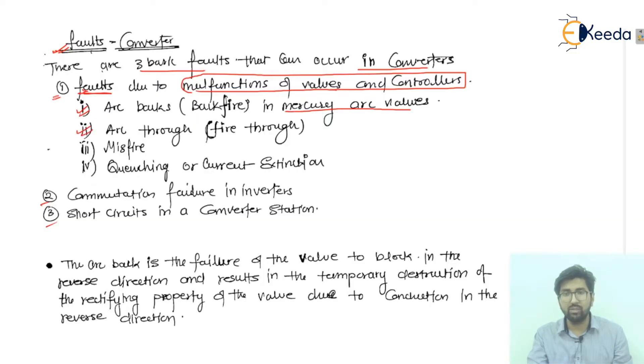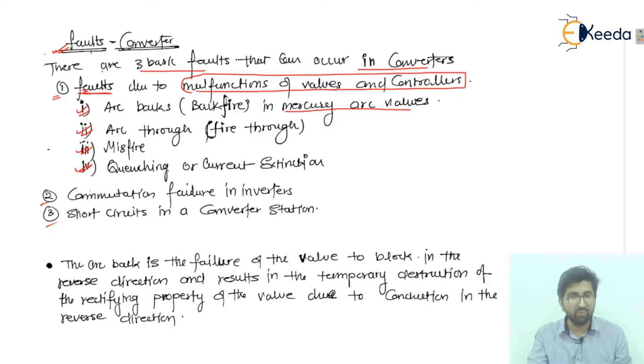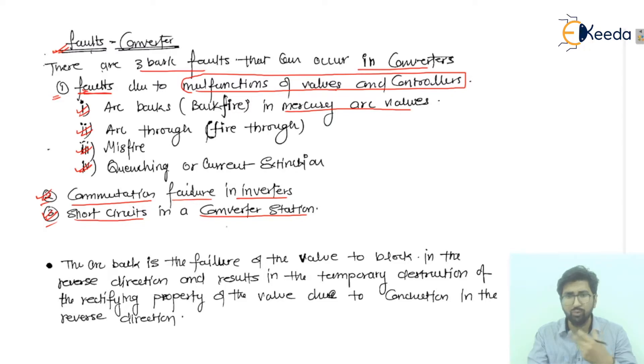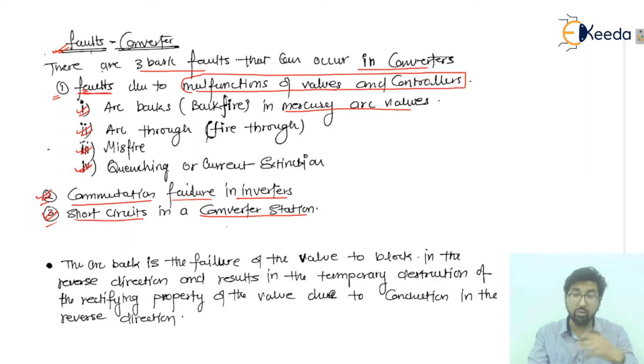The second point included is arc through and fire through, which we will discuss in further lectures, along with misfire, quenching, and current extinction. The second of the three basic faults is commutation failure in the inverters — on the inverter side there is a commutation failure. Point number three is short circuits in converter stations. If a short circuit condition arises, a huge amount of current flows through the supply lines and equipment, causing disturbance and breaking connection between healthy and unhealthy sections.